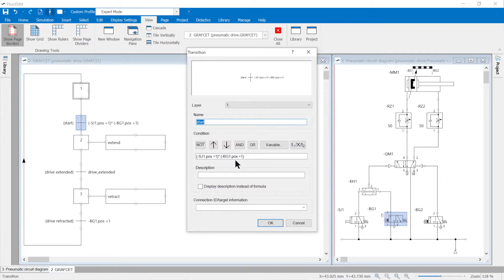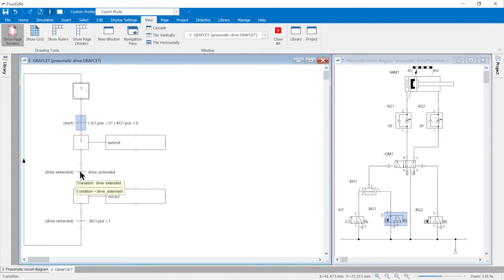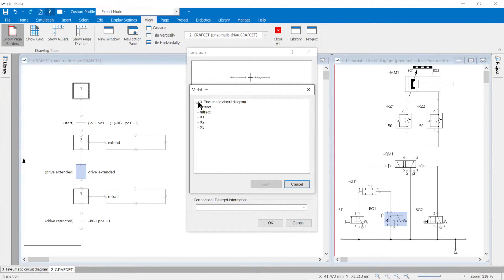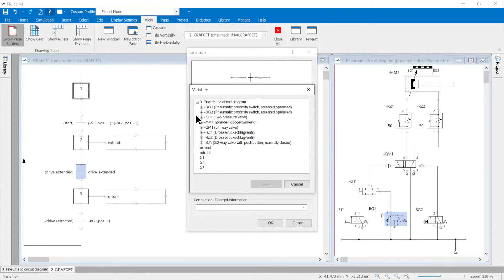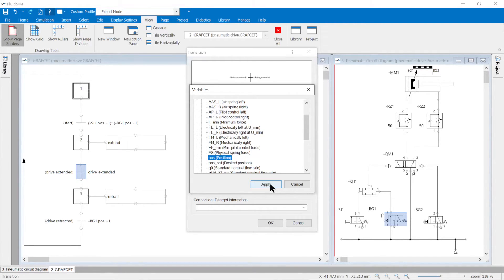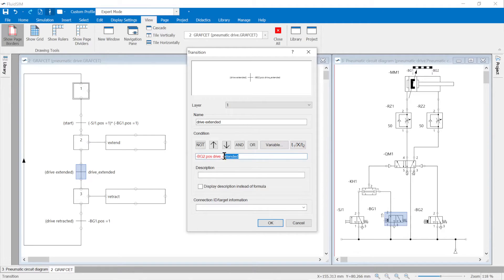The transition start is therefore an AND operation of the position variable of the start button SJ1 and the proximity switch BG1. The valves are actuated when the position variable is 1. The correct variable designation can be called up in the properties of the transition in the variable dialog. All components of the drawn circuit are listed there; clicking on a plus sign opens the next list level. Similarly, the transitions for drive extended and drive retracted are provided with position value 1 by comparing the position variables of BG2 and BG1.